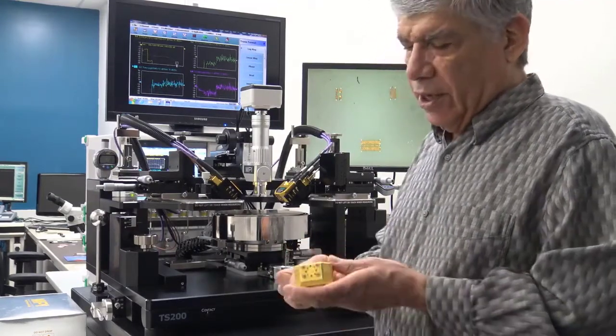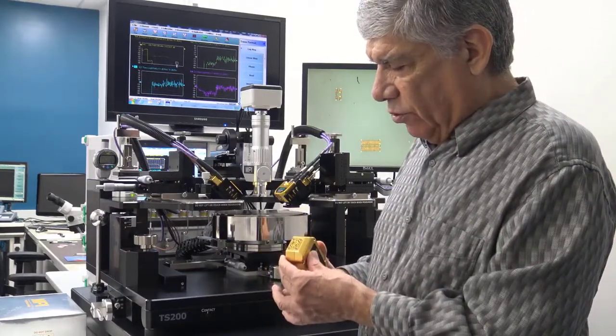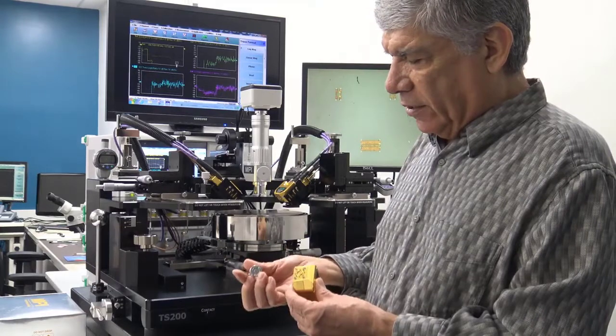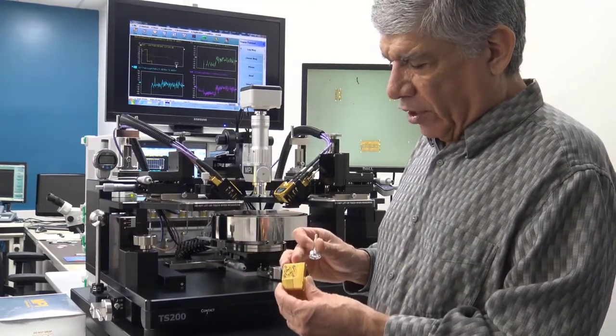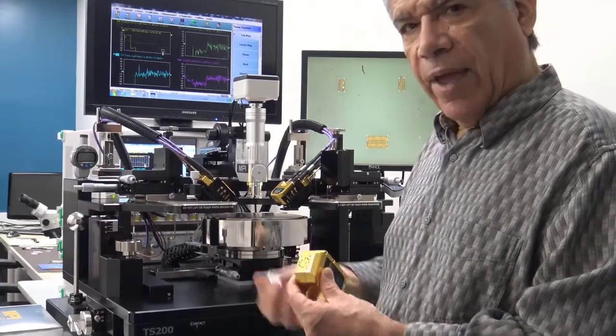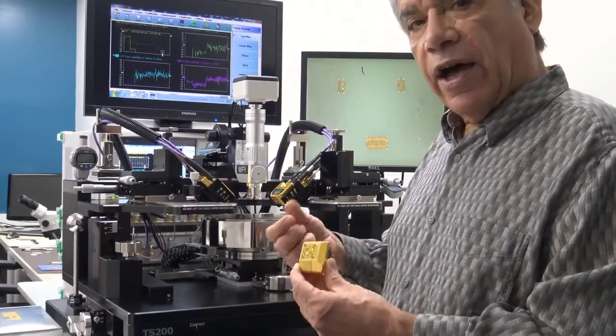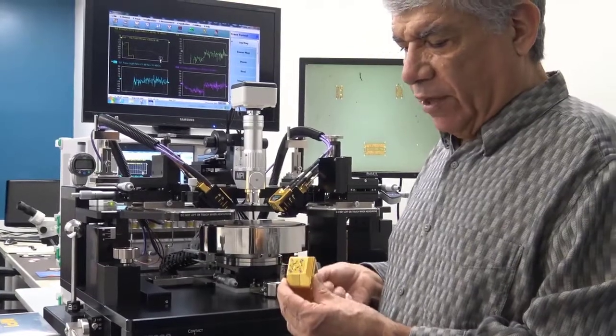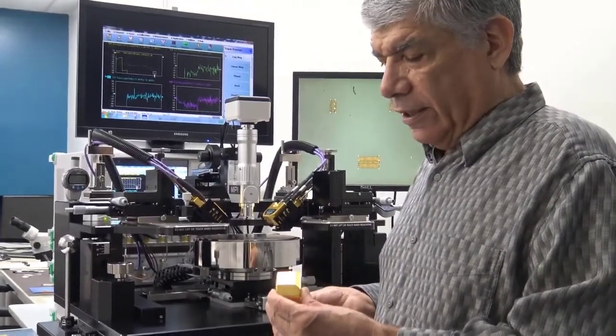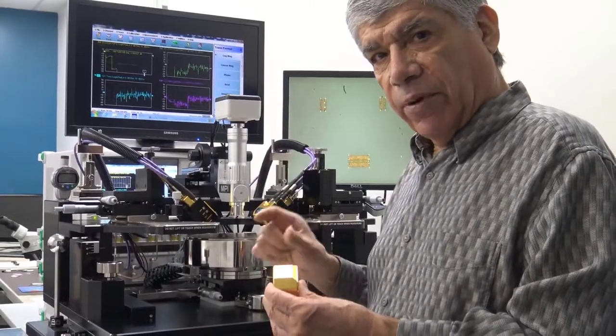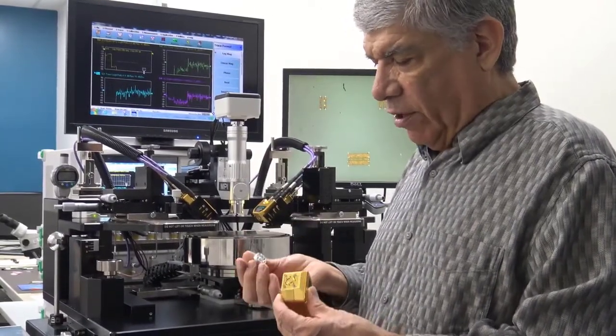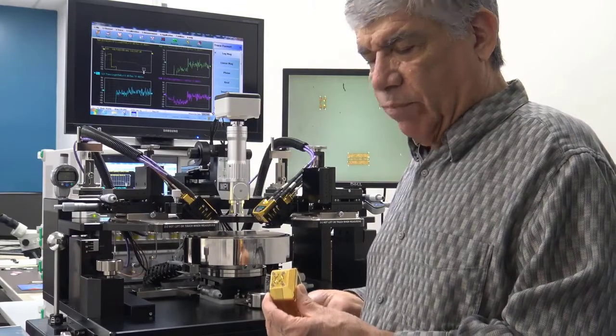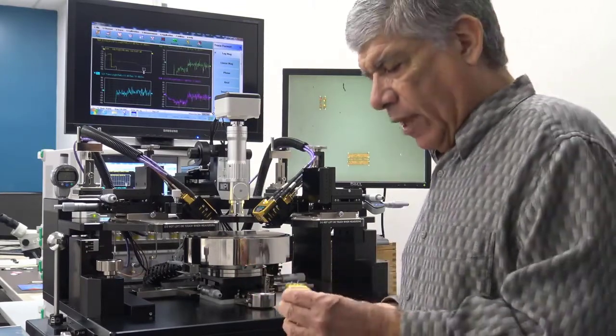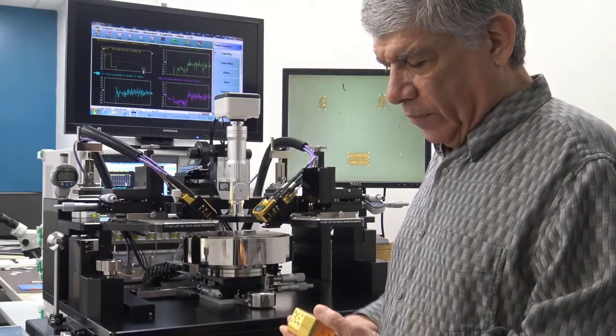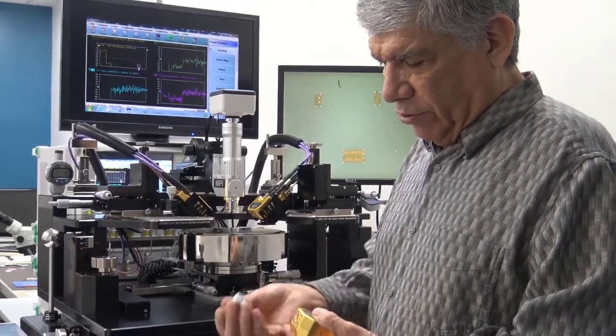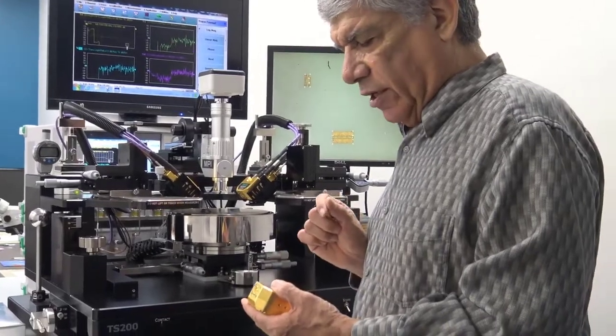What we use the flange for is to align the pins on the probe and on the module so that they create the mating interface, but without having to do the threading. The threads we found can wear and create some alignment issues after a period of time, and we're finding that the flange approach is providing much more repeatability. So that's what we're doing: connecting our probe onto the module using the flange interface.